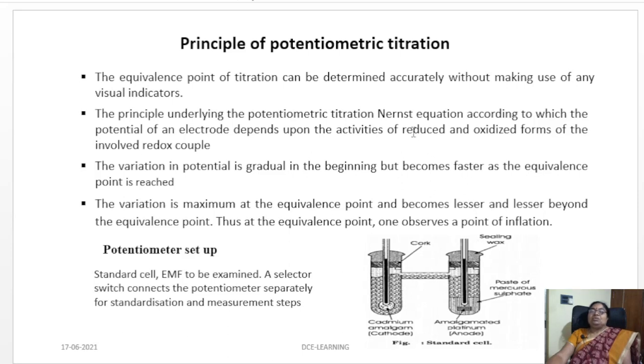Before we go for potentiometric titration, we have to set up the potentiometer. Whatever potentiometer is used should be standardized before using it for the potentiometric titration. So we are going to standardize it by using any one of the standard cells here.